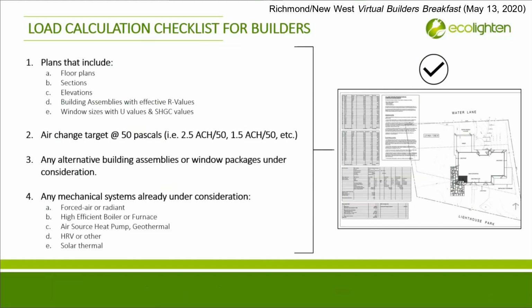Sometimes the plan submitted for building permit will evolve. That's normal. But if you know ahead of time what you want to ultimately build, it's critical that this information is given to your HVAC designer. For example, if you have a plan that, at post-occupancy, one room is going to turn into a different kind of use, it's best that your designer knows ahead of time. And finally, if you have already established what is not negotiable as far as systems go, it's important to make it clear. For example, radiant versus forced air, geothermal versus air-to-water heat pump, cooling or no cooling, etc. Sometimes clients already have their minds made up, and it's not worth the effort to try and convince them of other options.